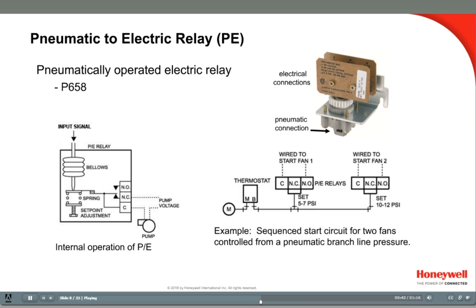In this example, a room thermostat's branch line pressure is switching two fans in sequence. The first fan starts with a rise in branch pressure at 7 psi, and the second fan starts at 12 psi. The fans will then shut off with a drop in pressure at 5 and 10 psi. This same controller's branch line could tee off to a damper or valve, creating control logic involving all functions of HVAC equipment.